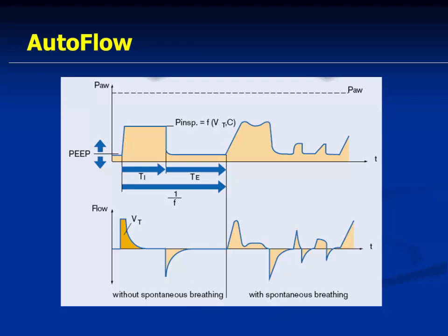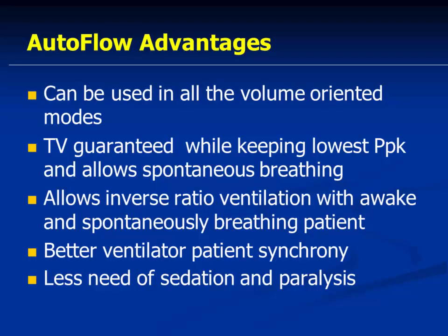You can see beautifully here. Without a spontaneous breath, everything looks so neat and clean. With a spontaneous breath, again, things are not looking neat and clean, but there is no asynchrony. It can be used in all volume oriented modes, tidal volume guaranteed while keeping lowest peak pressures, and allows spontaneous breathing. It allows inverse ratio ventilation with awake and spontaneously breathing patients, better ventilator patient synchrony, less need of sedation and paralysis.